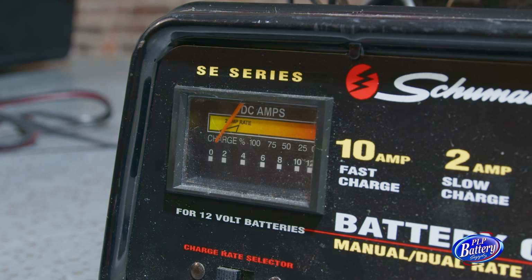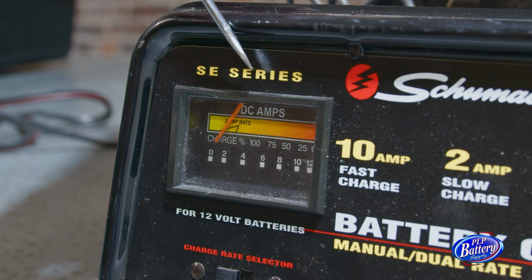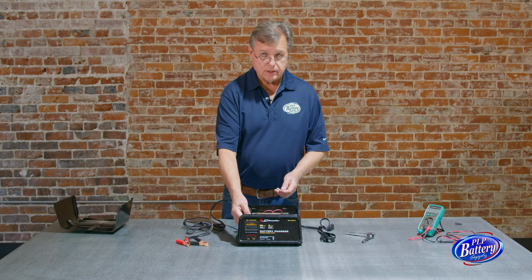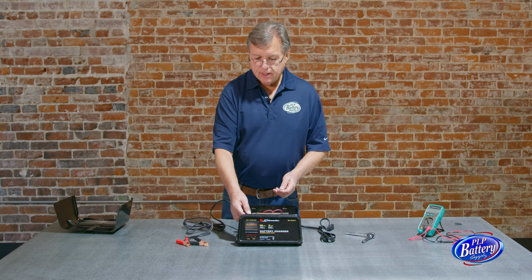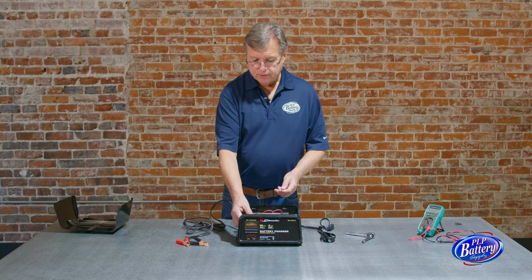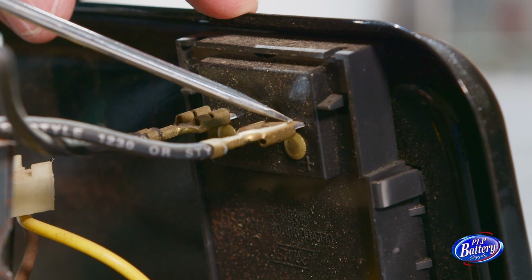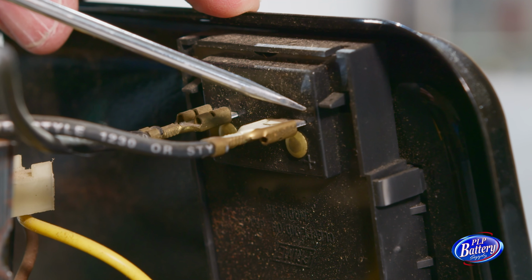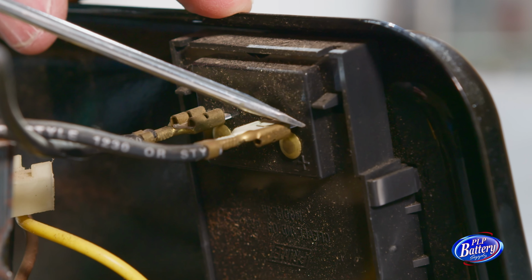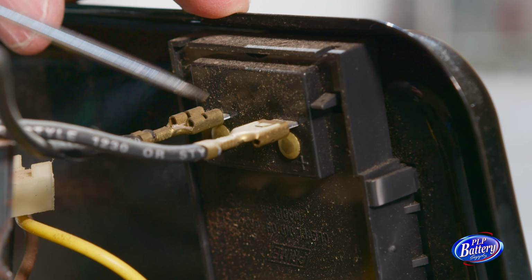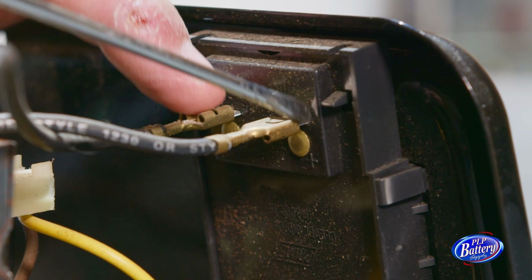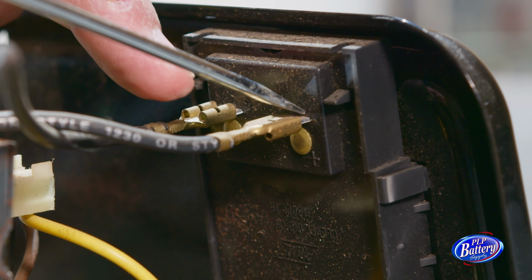If the continuity through the meter has failed, if the internal shunt has failed somehow, that's a heat-related issue. Normally if you look at the back of the meter right here, you'll see where it's melted and disfigured, and it's probably made some smoke. Again, pretty easy to diagnose, and those meters are generally available as a replacement part.